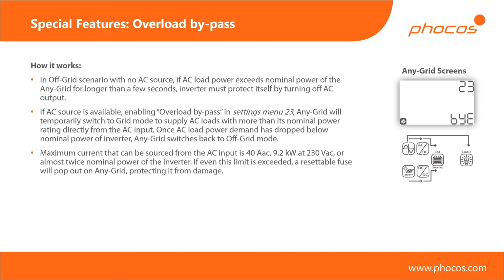And then it will provide you with up to 40 amps of AC power. If you multiply that together, 40 amps times 230 volts AC, that yields around 9.2 kilowatts of power that you can pull through the AnyGrid. So it's almost twice its nominal power rating. And in fact, for the 3 kilowatt, the smaller model, it's also 40 amps. So you could theoretically pull up to 9.2 kilowatts out of the 3 kilowatt model, simply because it's passing the grid power through to your loads if you exceed the 3 kilowatt nominal rating.